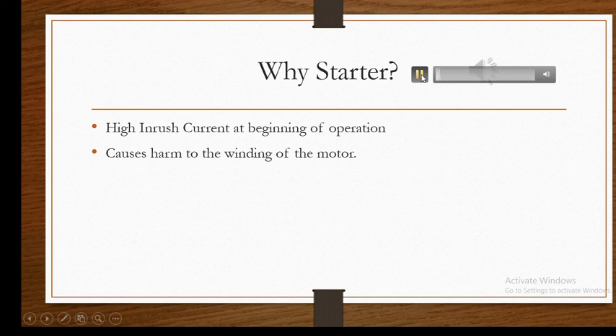It's important to understand why we even need starters. These induction motors deployed in industries are rated at extremely high power. When these motors start to operate, they draw a huge amount of current, which is also called the inrush current. This current is severely harmful to the windings of the motor and hence can cause some serious damage to the motor. So we need some circuitry or device or methodologies that can help us to reduce this inrush current and hence enable us to operate the motor more safely.